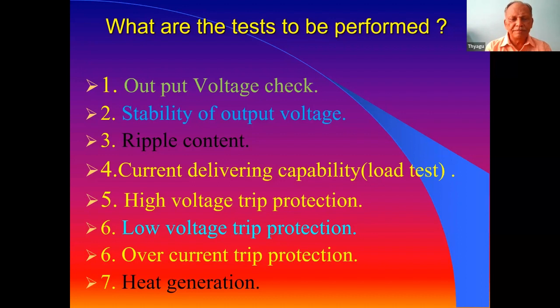Now, current delivering capacity - this is the most important thing. Checking the current delivering capacity is also known as the load test. That means if a power supply is rated for 25 amps, when we draw 25 amps, it should be able to maintain the output voltage at that rated current. So this is very, very important.